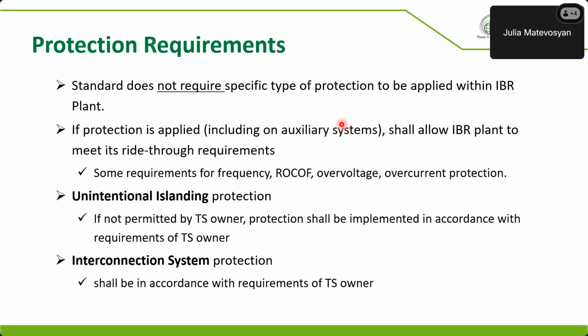The standard does not say that the IBR has to trip if the voltage stays below a certain magnitude for a certain duration, or if frequency remains below a certain magnitude for a certain duration. The standard does not require any type of protection. It is up to the plant designer and the OEMs to decide which protection is needed to protect their equipment, and then make sure that protection is not going to limit the plant from meeting its ride-through requirements of this standard, right? Okay, so that's the first bullet there.